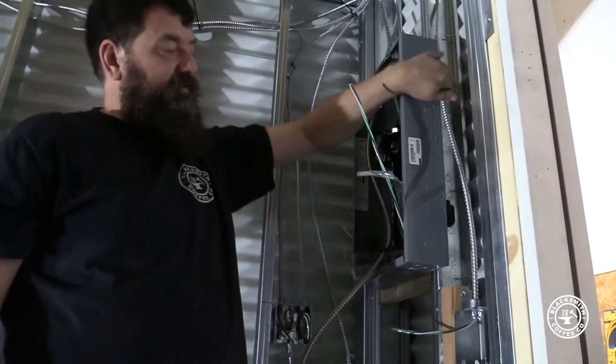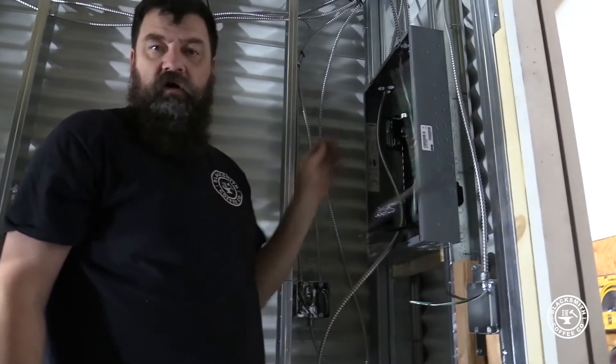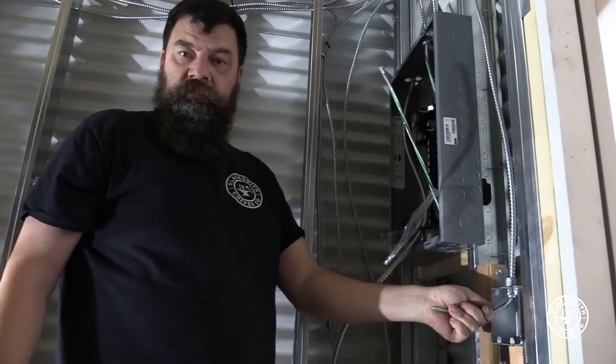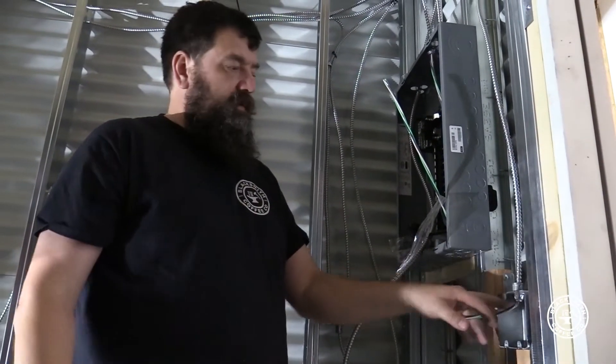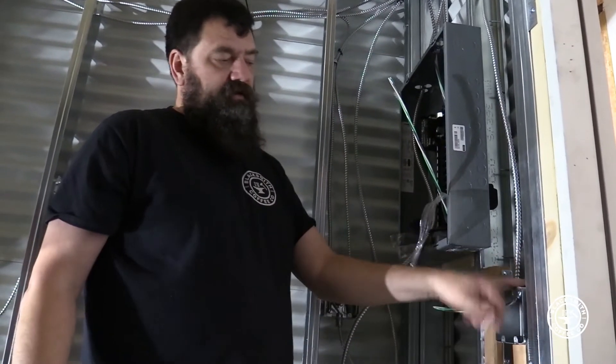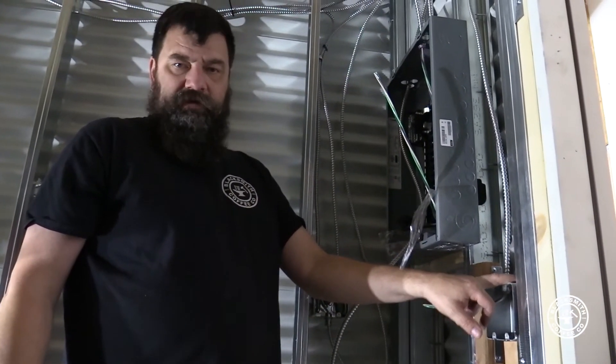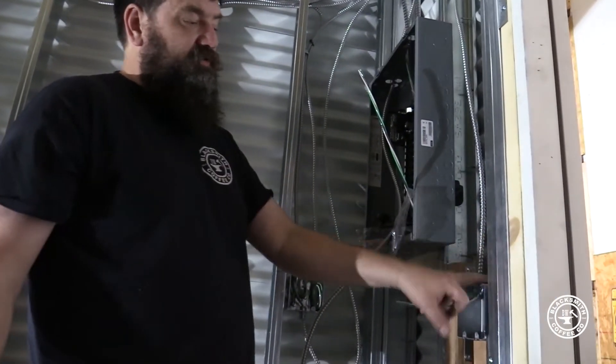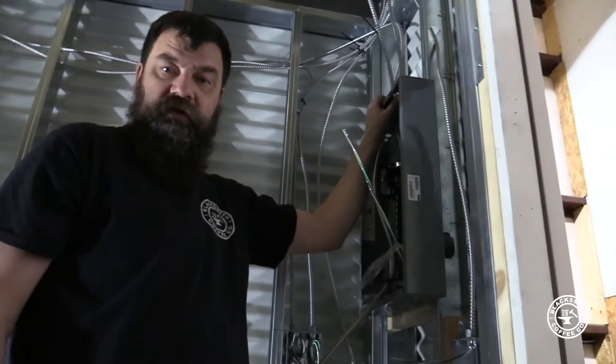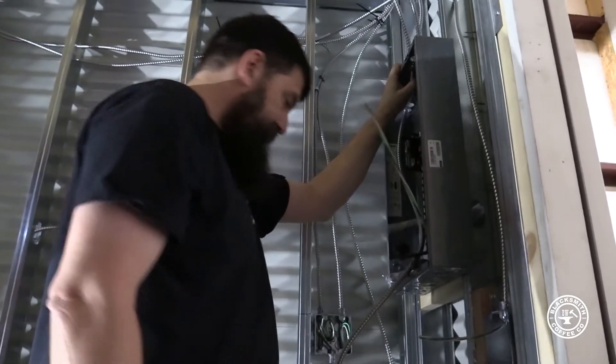So this is what you would call my load, meaning this wire is going to my lightbulb. Then I'm going to, this one here is going to be my line, which is going to supply power to my switch. And it's going to be my home run, which goes back here to my breaker box and goes to my 15 amp breaker. So now I'll put that in.